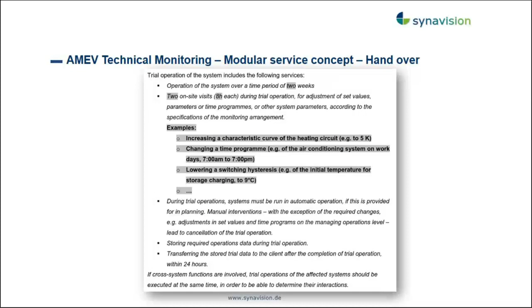Maybe you can overwrite the CO2 concentration in a seminar room just to see whether the air handling units and the variable dampers are reacting. So this is what you can specify, depending individually on the system that you're actually testing.